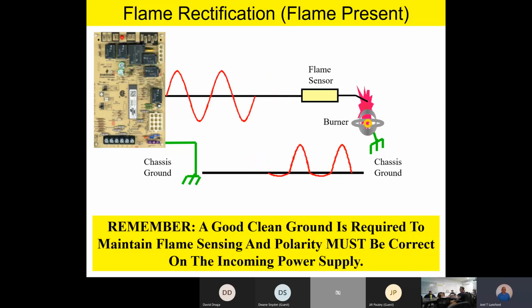So it's really important every year or during your cleaning check, clean that flame sensor. Make sure the ceramic on it is not cracked. And I recommend using steel wool or stainless steel wool to clean that flame sensor. Don't use sandpaper, because you can deposit little pieces of sand on there, and when you start the flame up, that sand can actually melt into a real fine little coating of glass, because that's what glass is made out of, sand. So be sure and clean that flame sensor with steel wool. Scotch-Brite works pretty good too, but do not use sandpaper, please.